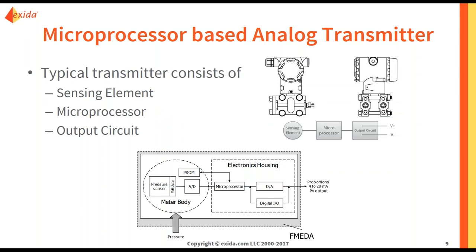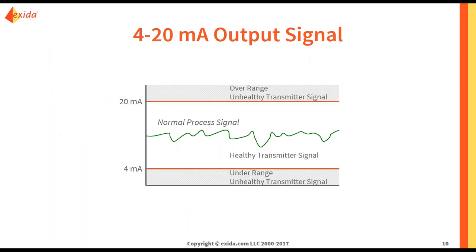A microprocessor-based analog transmitter is going to have a sensing element, a microprocessor, and an output circuit. The output gives a representation of the process value you are measuring in the form of 4 to 20 milliamps. That measurement might be a pressure measurement, a temperature measurement, a flow or level measurement, any measurement type. But it is going to give that in the form of 4 to 20 milliamps.